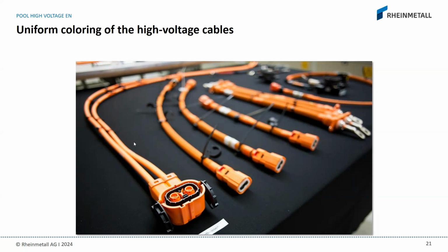I mentioned double insulation on these cables. Inside we have the current line, a metal line, surrounded by isolation. Then there's another metal mesh wrapped around the full cable from one connector side to the other - we'll see later why this exists - and around that another layer of isolation. This means if a cable is damaged, cut, or scratched, it cannot be repaired. You always have to change the full harness, meaning all the parts connected with that cable.